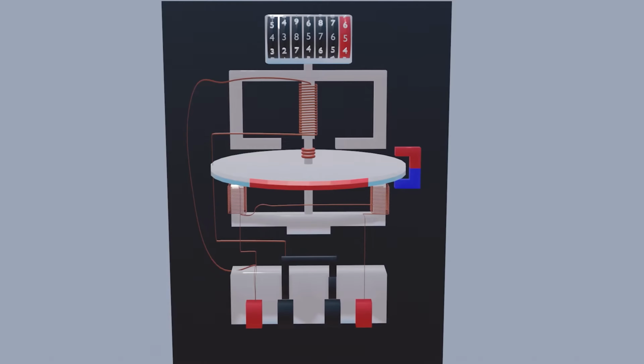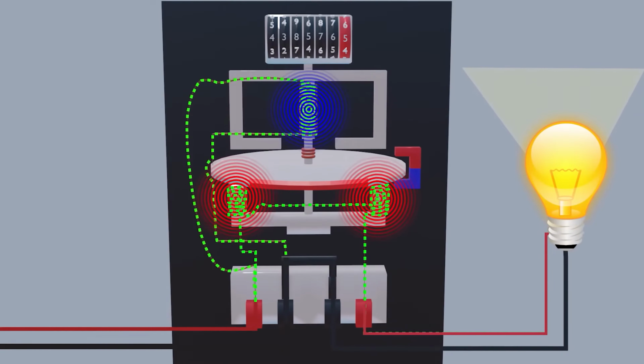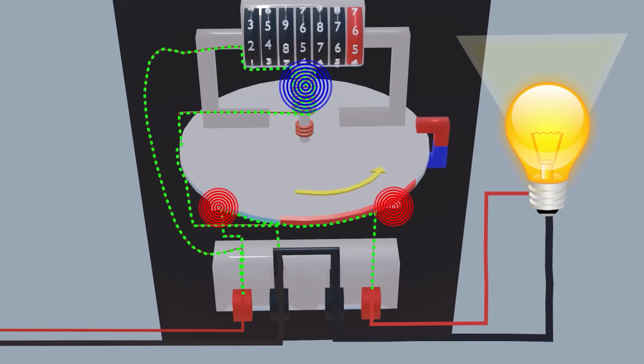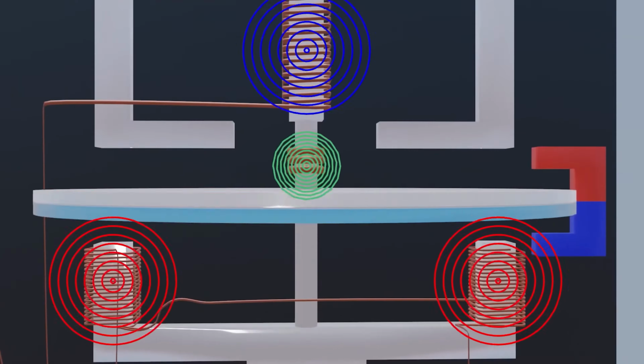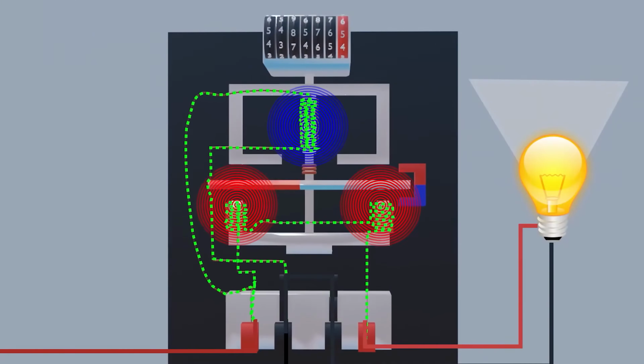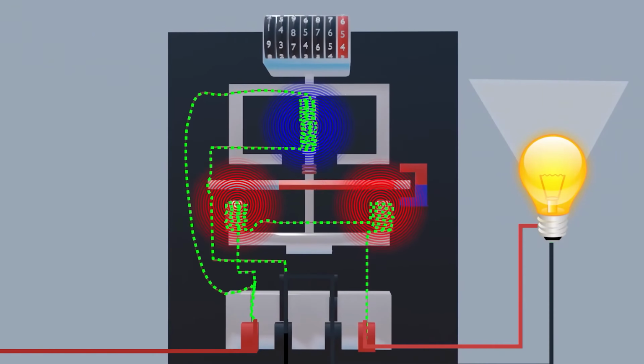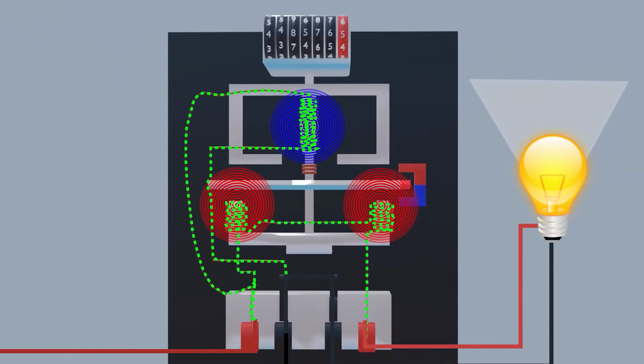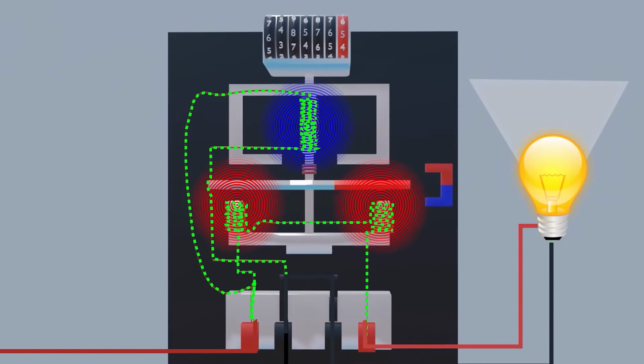Basically, the meter has current coils and voltage coils. When electricity passes through your house, these coils generate magnetic fields that interact with the aluminum disc, and this interaction makes the disc spin. The more electricity you consume, that is, the higher the power, the faster the disc spins, and the longer the devices stay on, the more turns the disc makes. A system of gears connected to this disc counts the number of turns, and that's what translates into kilowatt hours.